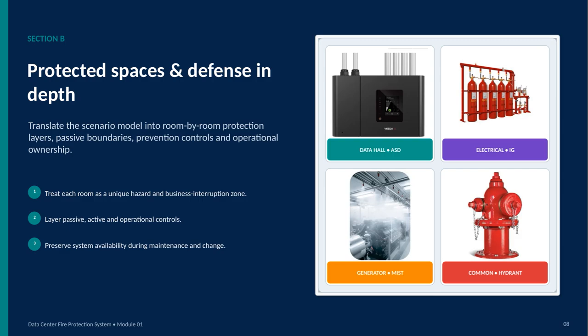The data hall uses ASD, or air sampling detection, while electrical areas use IG, indicating an inert gas approach. Generators are associated with mist protection and common areas with hydrant coverage. These examples show how protection is matched to the room, its equipment, and its consequences.